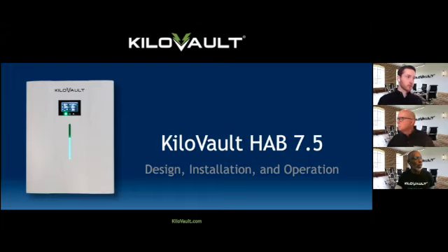I'll answer a couple quick ones here. A good question actually from Andrew. Can you hook an MPPT charge controller up to the HAB? Yes, absolutely. We spent a lot of time focused on the inverter charger side of things, but yes, these can be DC coupled without issue. A lot of the set points are pretty much the same as you would use for the AC charger of an inverter. You just need to make sure that the absorb float voltage and absorb time are programmed according to the HAB specs.